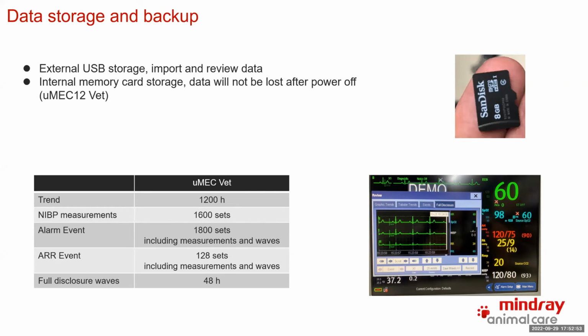And also we have the 48 hours full disclosure waveform. The full disclosure waveform is very important because a lot of patient monitor products can store the trend for the parameters, but especially for the ECG parameters, sometimes we like to review more details of the ECG waveforms, not the trend, because the trend can only provide the trend wave for the heart rate. If we can store a long time of full disclosure waveforms, especially the ECG wave, the doctors can check all the detailed information through the original waveform on the patient monitor itself, and have a better idea of what's happening during the surgery from all these details. So with this storage function, it's very good.